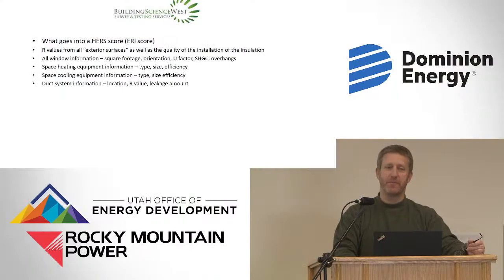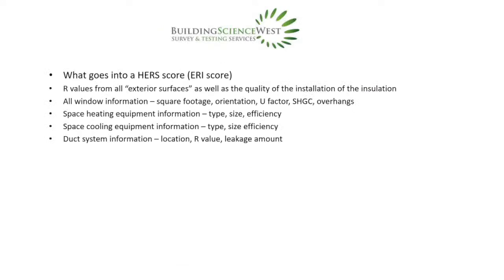Space cooling needs to be sized correctly, and the duct system needs to be sized correctly for the system and the home. That information goes into the duct system inputs: the lineal feet of ductwork, the location of the ductwork, whether it's in unconditioned space, and the R value of the insulation on that ductwork, which plays a large role in the efficiency of the home.